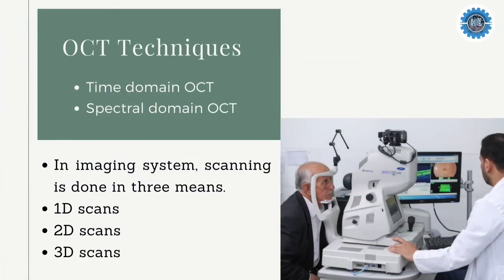The Optical Coherence Tomography technique can be applied by two methods: the first is Time Domain OCT and the second is Spectral Domain OCT. In an imaging system, there are three means for scanning — one is to scan the object in depth and the other two are used to scan transversally. 1D scans are labeled as A-scans, while 2D scans are labeled as B-scans.